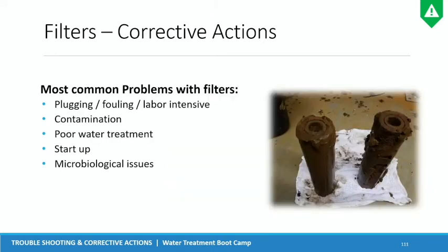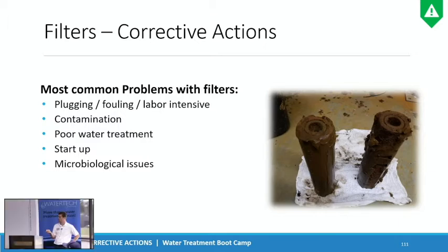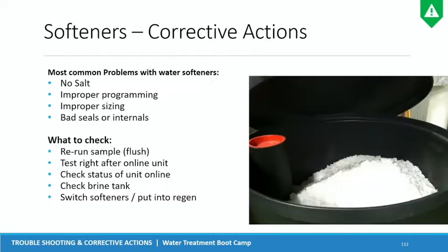So that's a customer of mine, and that was the worst chilled water loop that I have ever seen in my life. The loop literally looks like that. So it was really bad, but we got onto it, and he was on top of filter changes, flushing his system out. I am happy to say that loop now is clear water when you grab a sample. So it took a lot of time. We're talking about a year of doing this to get it back to where we wanted. But that's what happens if we do have poor water treatment and no filtration. Those were in for, I don't know how long they were in for, prior to me being there.